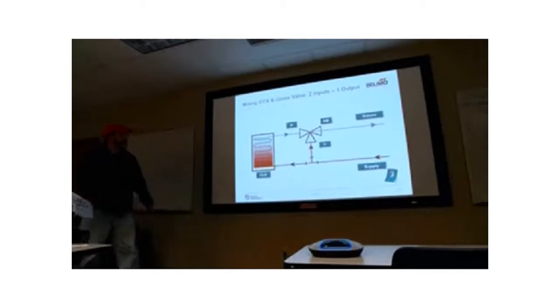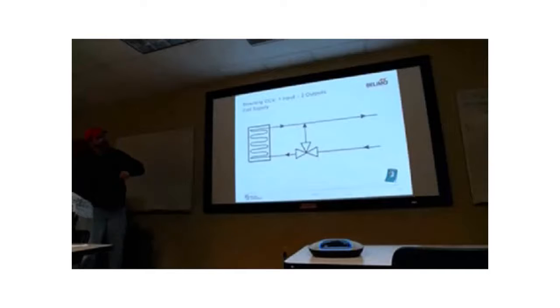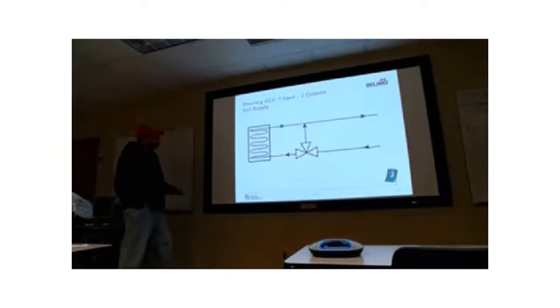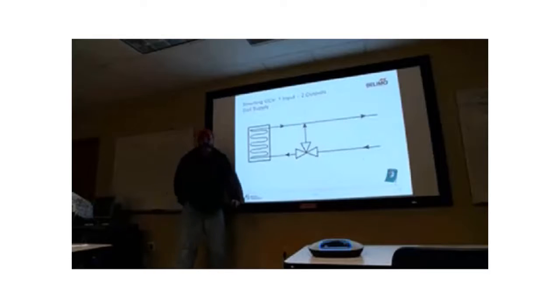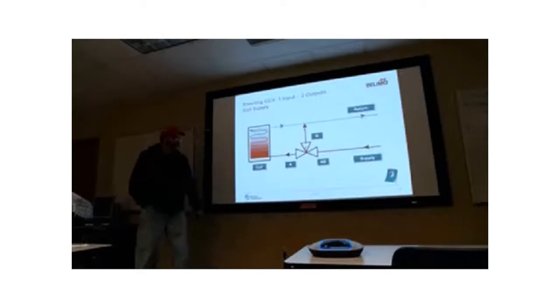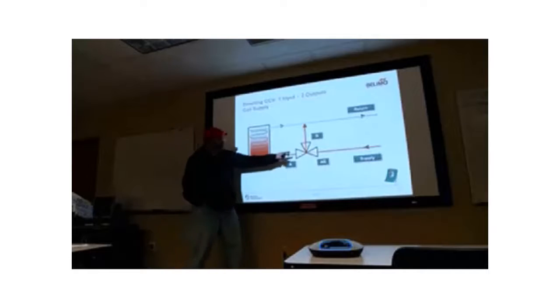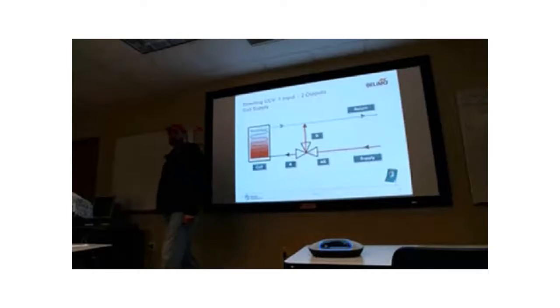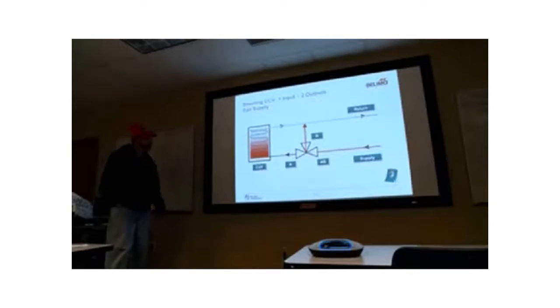That's a mixing application. If it's diverting, if you find the three-way valve is on the supply side of the coil, then it's a diverting valve. But it does the same thing, really, right? It really does the same thing in terms of capacity control. It's still controlling the water flow through the coil, except now you're diverting the water around the coil rather than getting it on the backside.